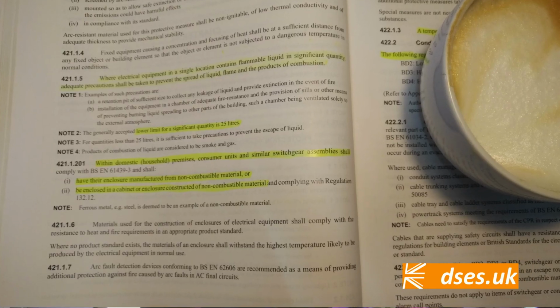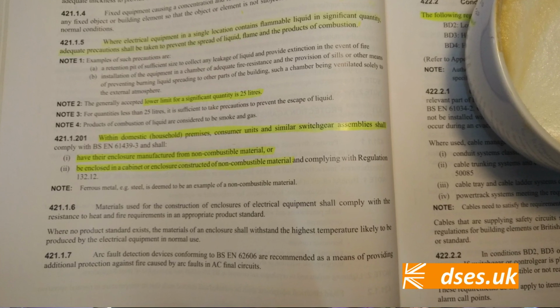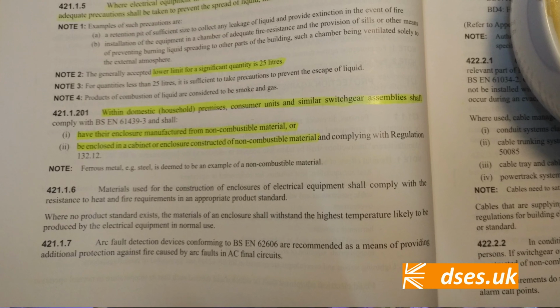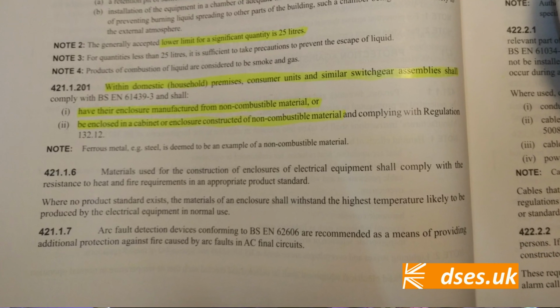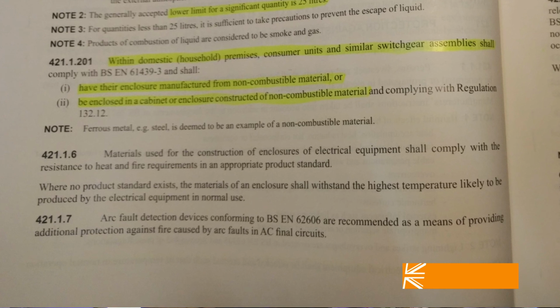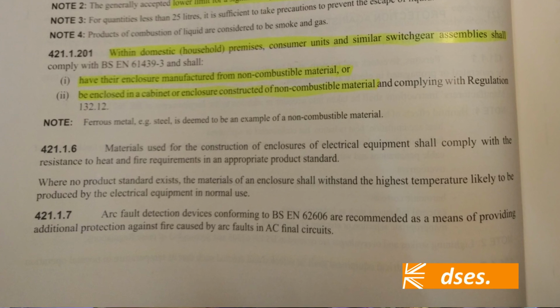At the time of recording, we don't know what 18th edition Amendment 2 is going to say when released in 2022. It may beef up the current wording of 421.1.7, which currently only recommends the use of AFDDs to start mandating them. And if it does, then it will apply to that point forward for new installations, new circuits, and new consumer units being bunged in.